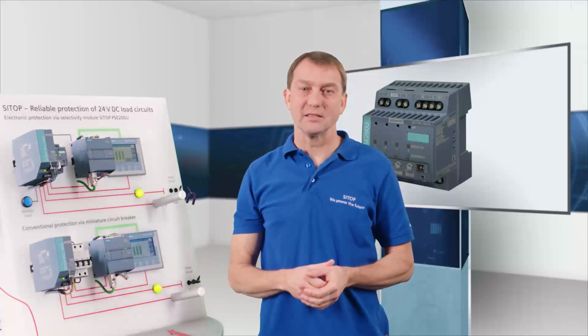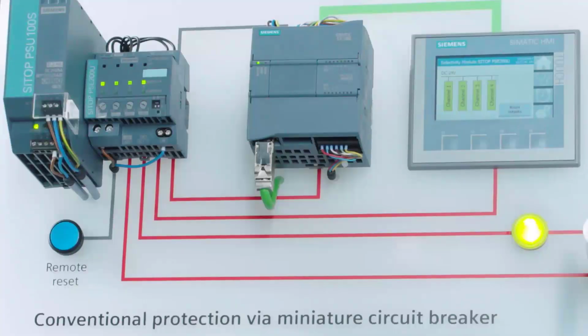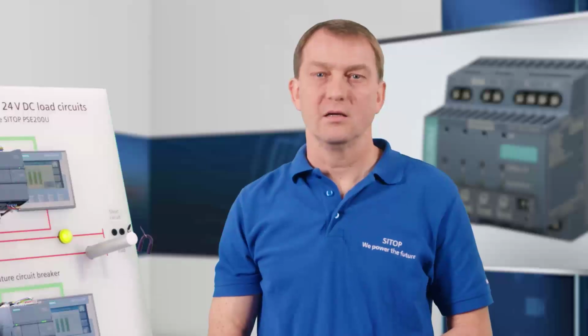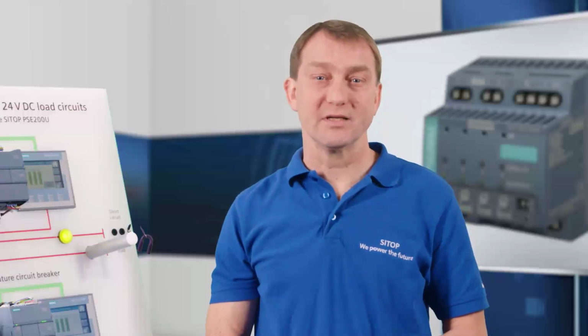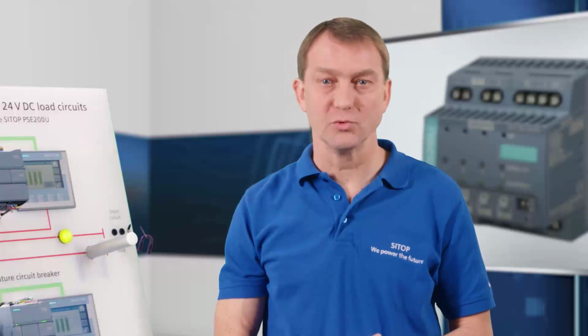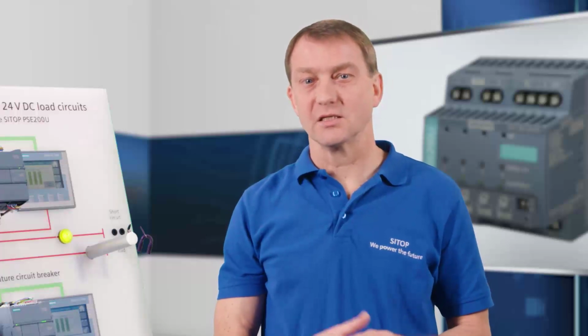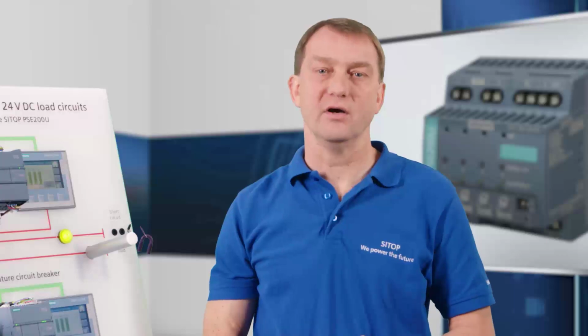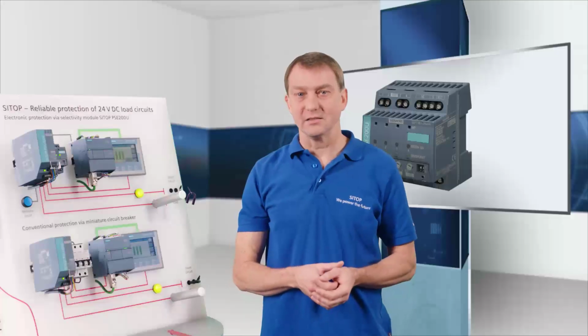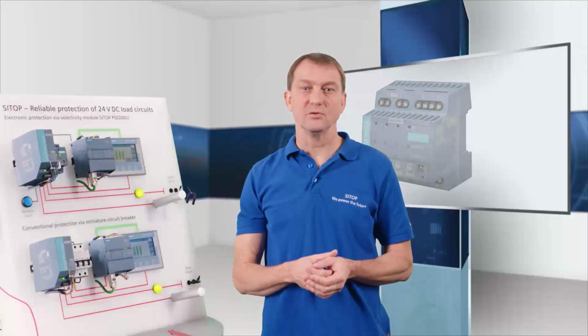Using the measured currents for the individual outputs, you can easily set the tripping current. Values from 0.5 to 3 amps or 3 to 10 amps can be specified according to the device type by means of stepless adjustment. In this way, the tripping current can be adjusted slightly above the maximum current with much greater precision, which means that the selectivity module trips reliably in the event of a fault. This makes commissioning and service work in particular easier.